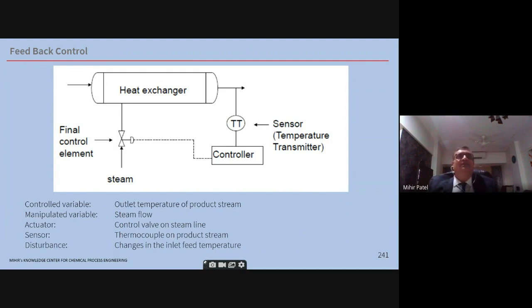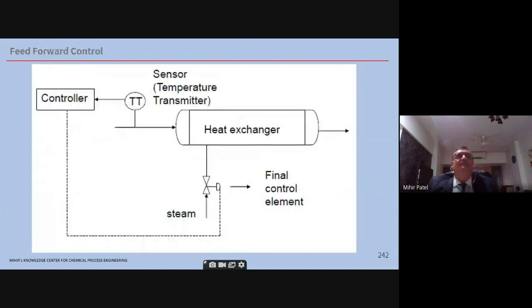Okay, so this is where the feed forward system is better. The process engineer defines these systems. So in a feed forward system, for example, in the exchanger, your steam is coming at 50 degrees, you are heating to 80 degrees. Let's say the inlet steam changes from 50 to 52. So this 52 then sends a signal to the steam and you reduce it. That means your outlet parameter of 80 is maintained at 80 throughout. This is the advantage of a feed forward system. Your lag time is reduced, so your final process outlet temperature is more uniformly maintained in feed forward control. But then you have to know the variability of the upstream temperature in order to finalize this.